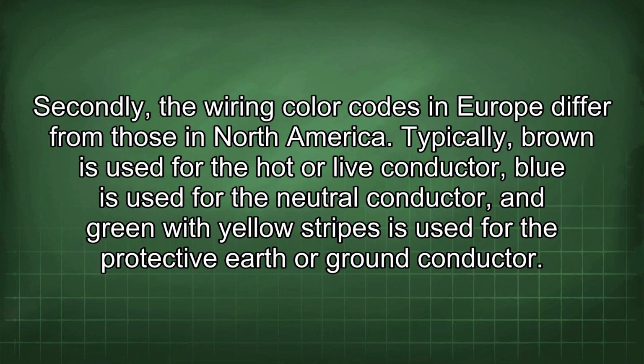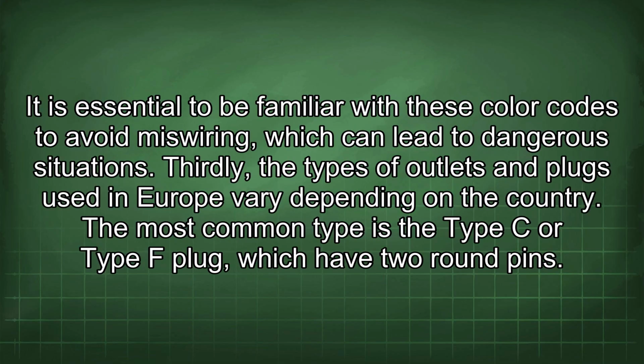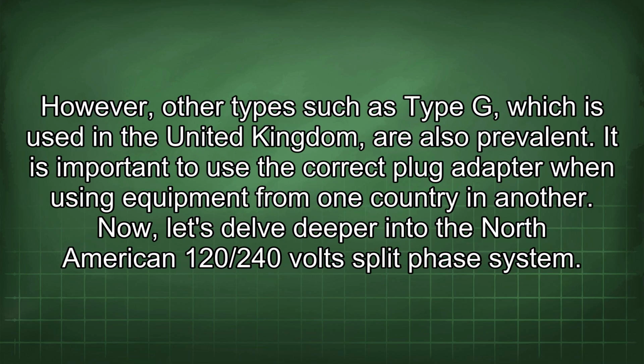Secondly, the wiring color codes in Europe differ from those in North America. Typically, brown is used for the hot or live conductor, blue is used for the neutral conductor, and green with yellow stripes is used for the protective earth or ground conductor. It is essential to be familiar with these color codes to avoid miswiring, which can lead to dangerous situations. Thirdly, the types of outlets and plugs used in Europe vary depending on the country. The most common type is the Type C or Type F plug, which have two round pins. However, other types such as Type G, which is used in the United Kingdom, are also prevalent. It is important to use the correct plug adapter when using equipment from one country in another.